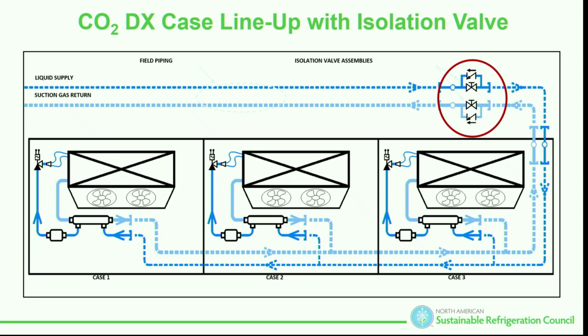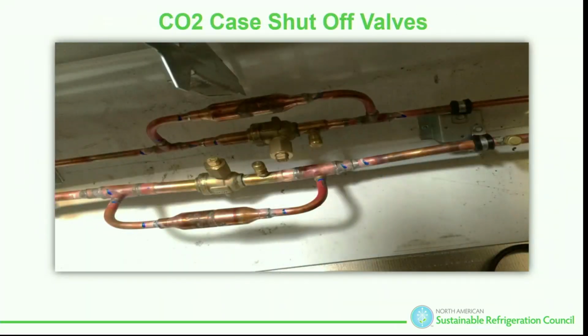Because remember, CO2 has a very high expansion rate, right? So if I'm coming over and I got liquid in there and I isolate it and I didn't follow the procedure I was supposed to, and I just start hitting that with 87-degree water, what's going to happen? I could have a leak event, right? Small one. As Paul Burnett would say, there's little reliefs on every single U-bend of all those coils. But just to let you know, they're not resettable. So just to let you know, when they go, it's a garment changing event. Yeah, make sure.